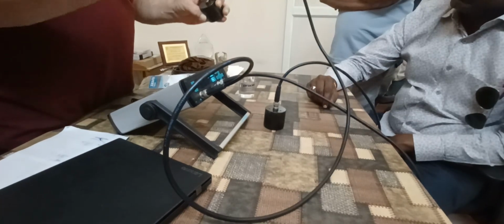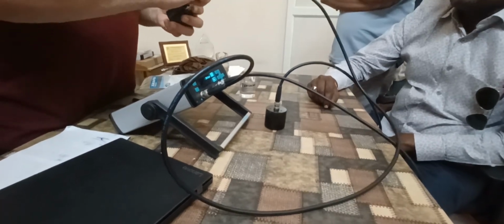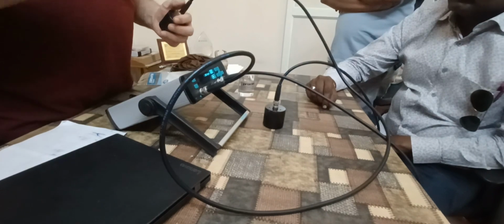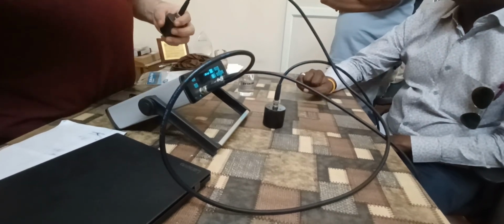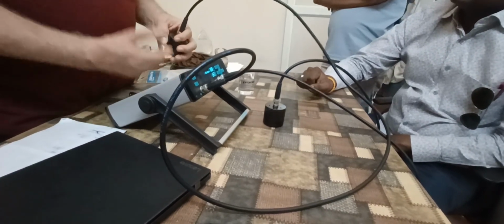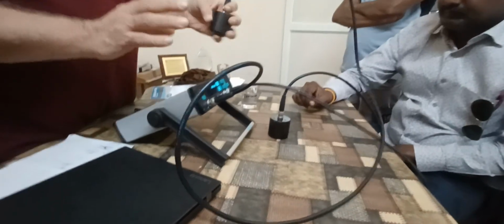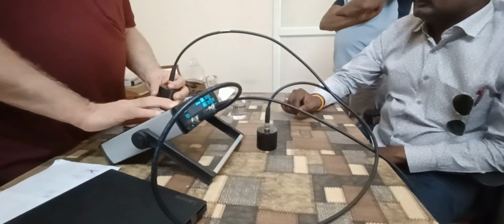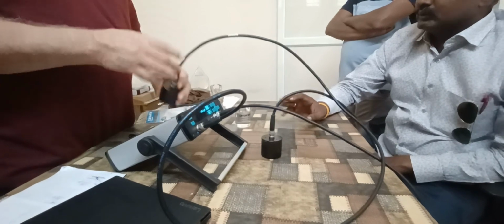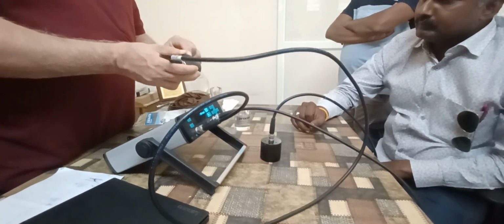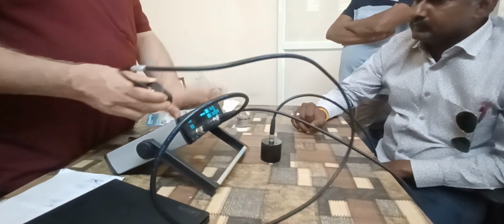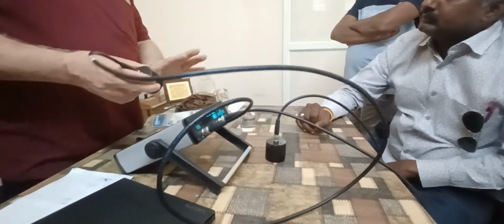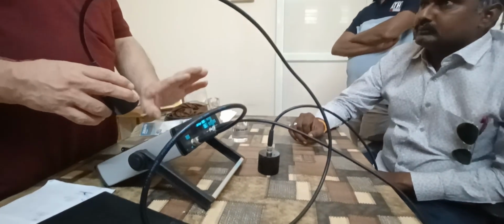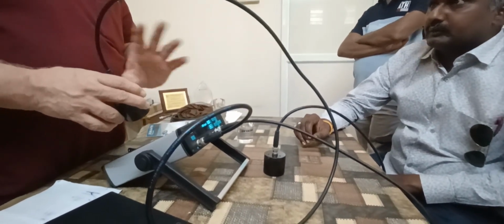And if you keep using it like that, it will get short. The pulse will go back and hit the PCB. After some time, if it keeps happening, the PCB will go. It is very expensive. The PCB is around 90,000-95,000 rupees. And this transducer also, don't drop it. It is a 24 kilohertz transducer. In the instrument, you can use it from 24 kilohertz up to 500 kilohertz. This instrument is compatible with all that.